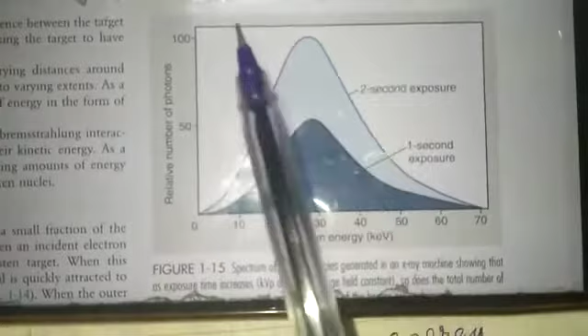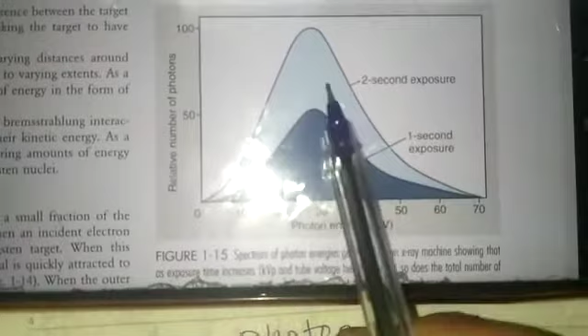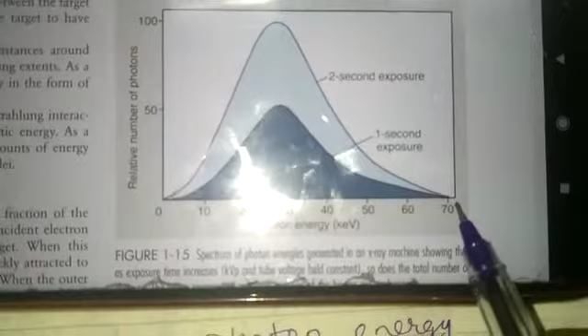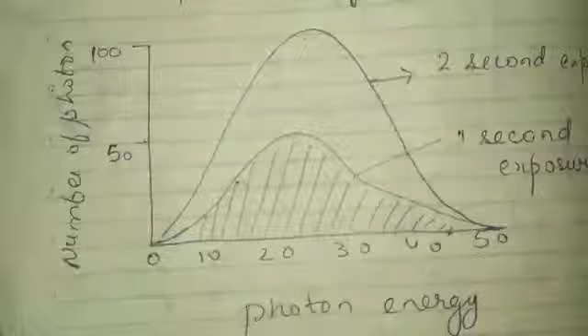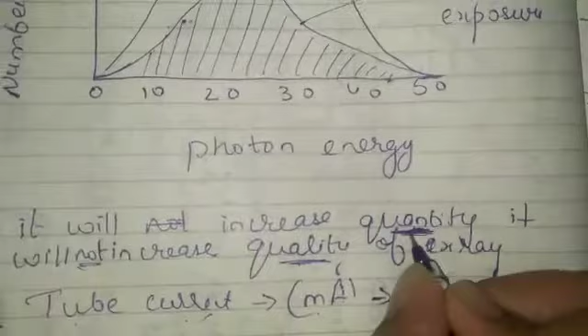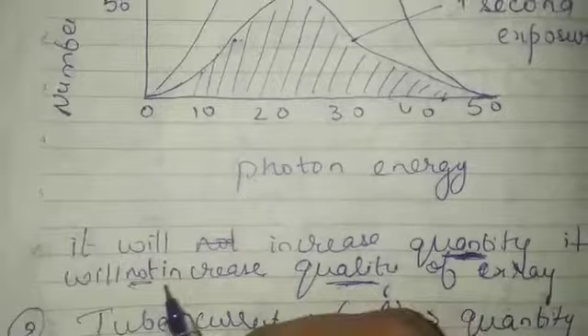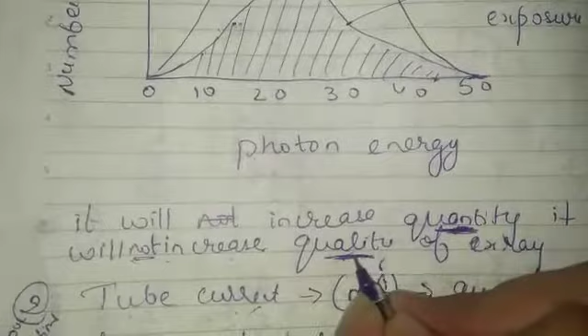If we increase the exposure time, you can see in the first exposure the photons generated is 50. In the second exposure the photons generated was 100. So if we increase the exposure, the number of photons is increased, but you can see over here it's 70 only from both. So the photon energy is unchanged. Exposure time will increase the quantity, meaning the number of photons, but it will not increase the quality of X-rays. So this is about the exposure time.